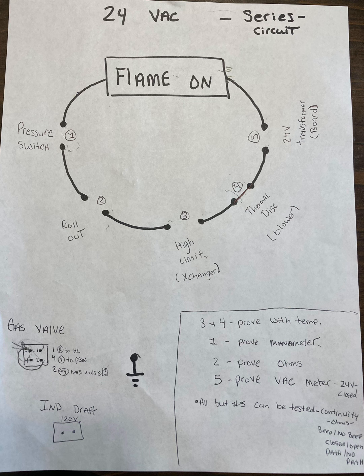Did it open up at 120 degrees? If so, it's lying. That's a bad switch. It was rated for 180, or whatever the switch in question is rated for. So we need to keep an eye on that, and we can test it very easily just by running sequence. What temperature was it? If it did cut out at 180 degrees, now it's your job as a technician to find out, why is my heat exchanger getting this hot?